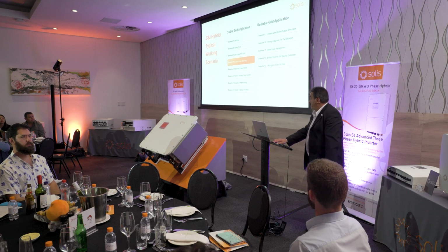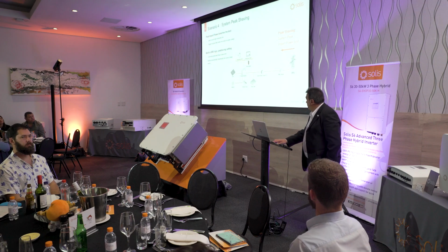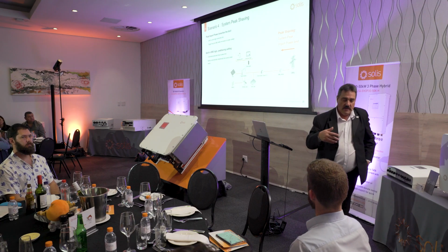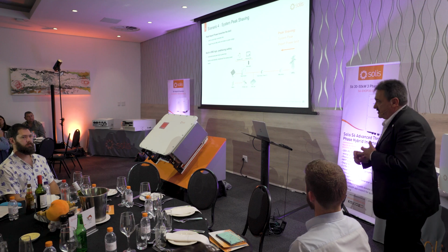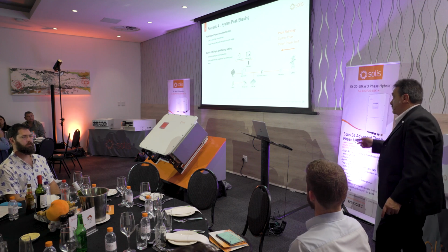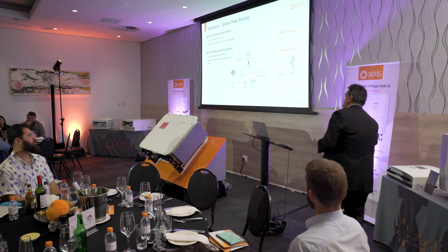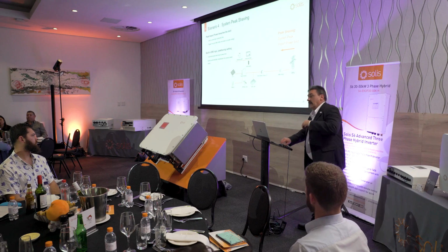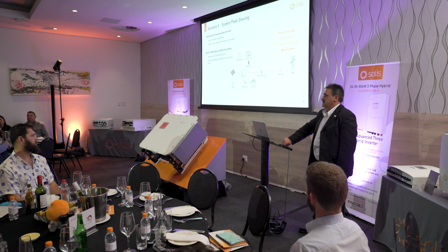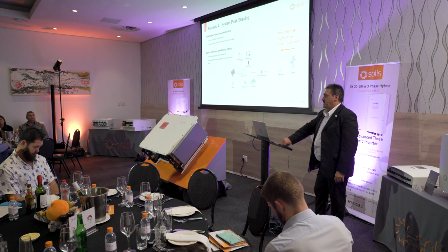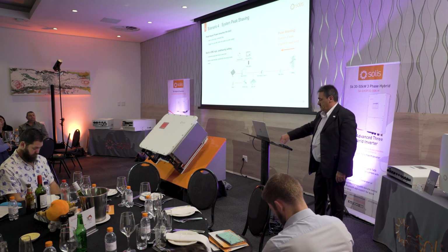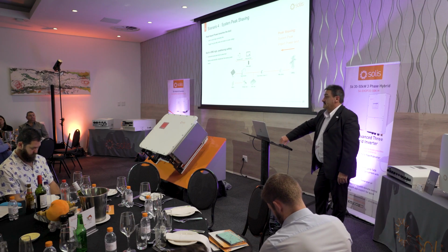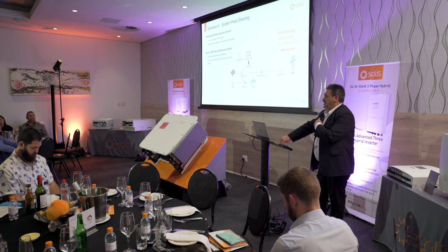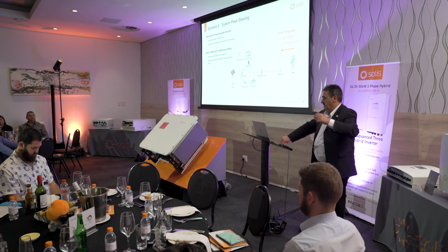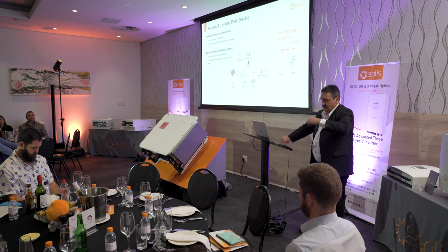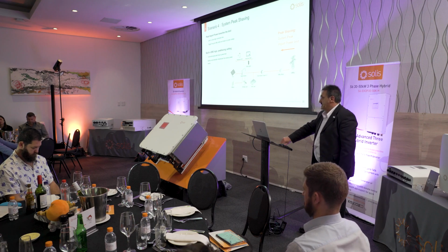So it's a very strong attribute. And then obviously arbitraging, using time settings where you can export or not export, pull in power or export power. Arbitrage is very strong. We sell a gazillion inverters in Europe, and 99% of all those inverters sold, the backup ports are not even connected. But they work for energy arbitraging every day of their life, energy in, energy out, and that's all they do with it.